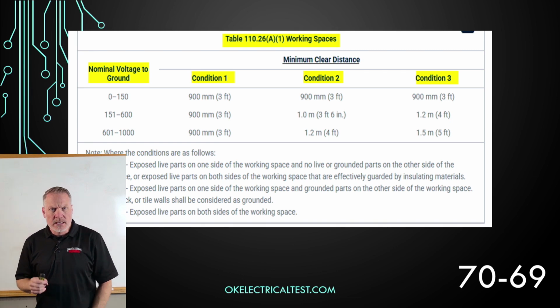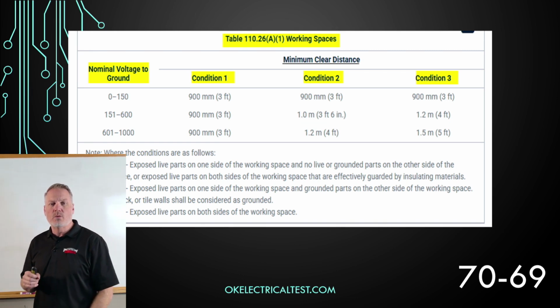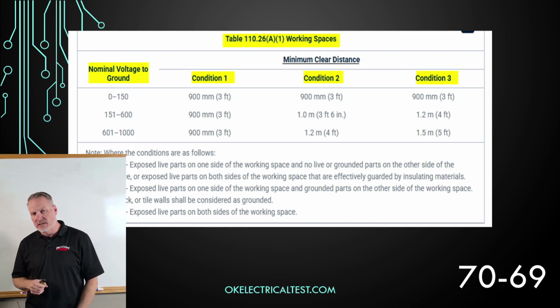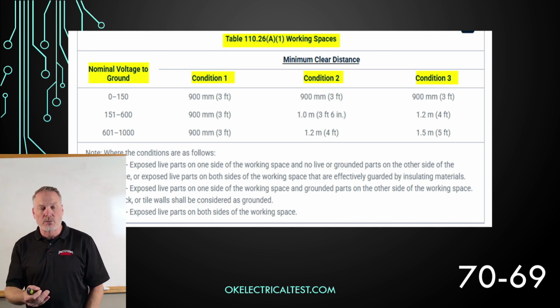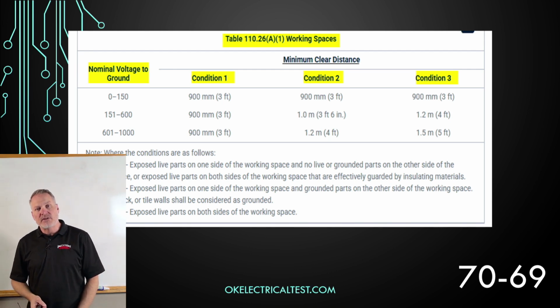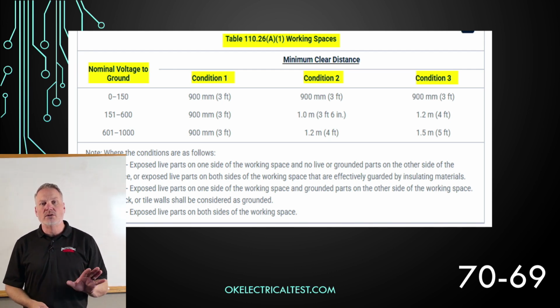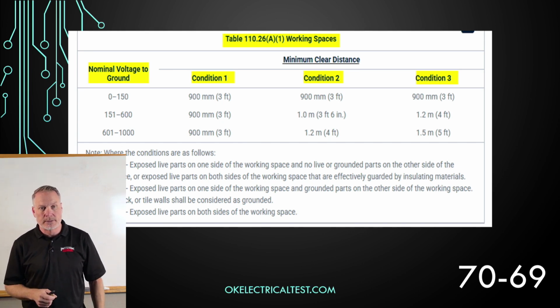And so table 110.26(A)(1), that's our working spaces. We need to read all these different headings to understand exactly what the table is talking about. So again, it's the depth of the working space, and that's going to vary depending on our voltage. Over on the left-hand side, we've got our nominal voltage to ground.